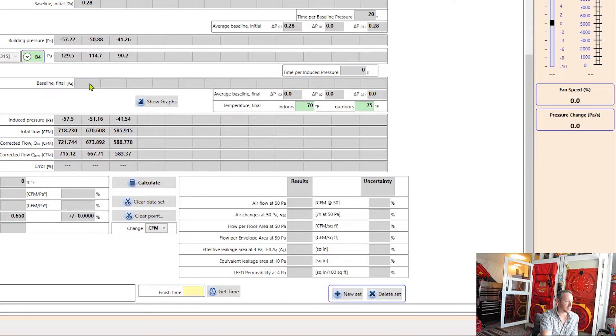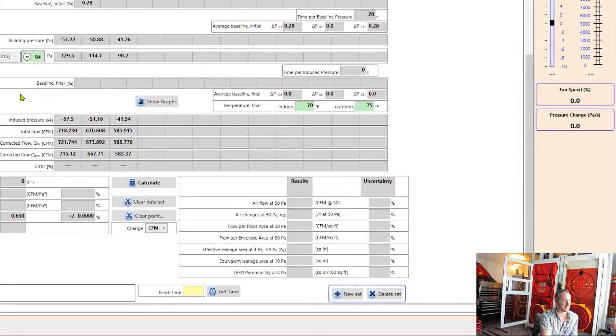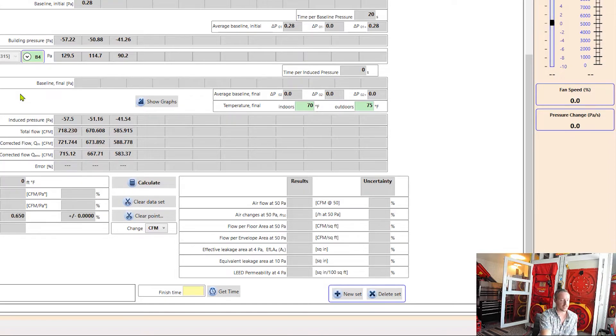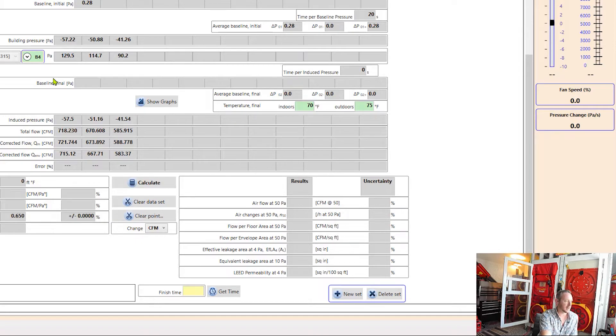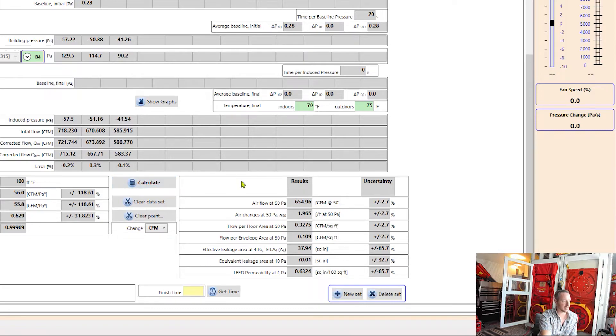If I wanted to, I could do a post baseline. But for the sake of time today, we're not going to do that. If you're just doing a ResNet test, they don't require you to do that. However, if you're doing tests to other standards, then it does. So this depends on why you're doing the test and what your standards require, if you want to do that final baseline or not. But for now, we'll go ahead and hit calculate and see what we get. And now I can see all of my results here.